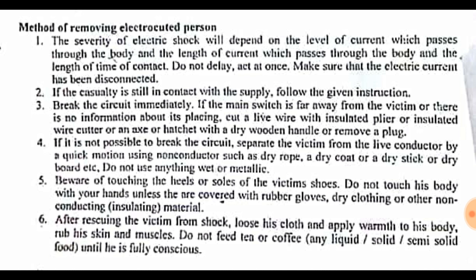Method two: if it is not possible to break the circuit, separate the victim from the live conductor using a quick motion with a non-conductor such as a dry rope, a dry coat, a dry stick, or any non-conducting material. Do not use anything wet or metallic, as it may also give you a severe shock.